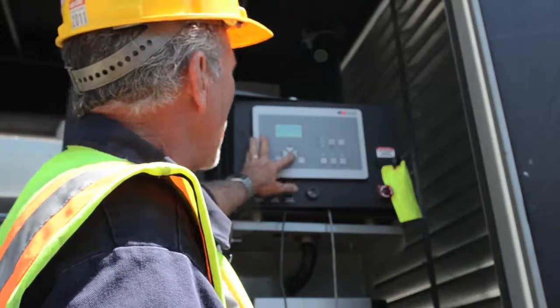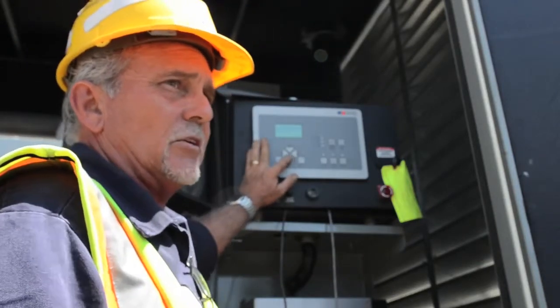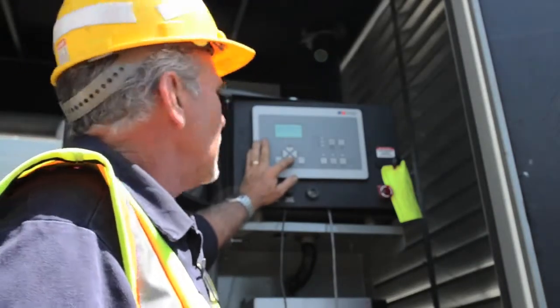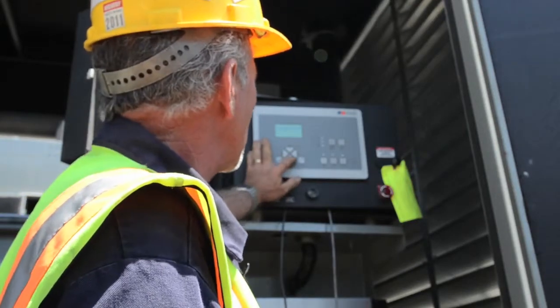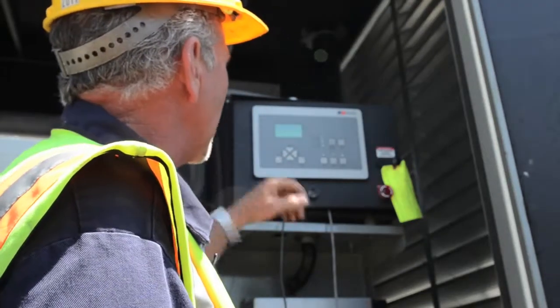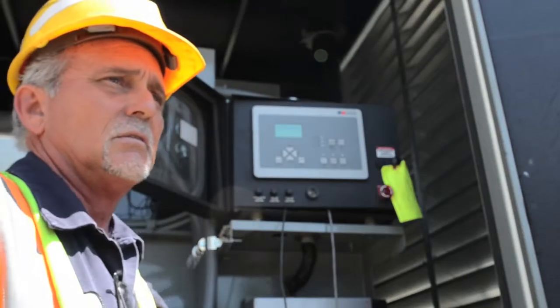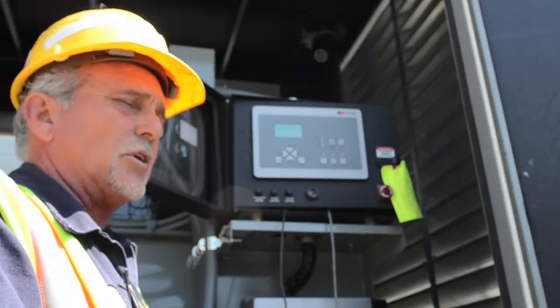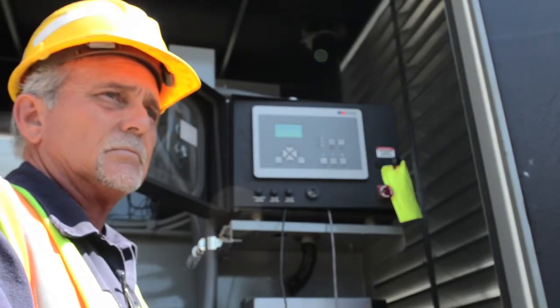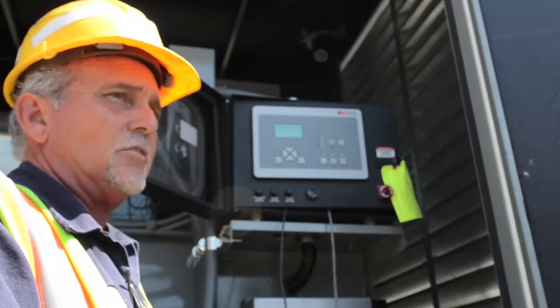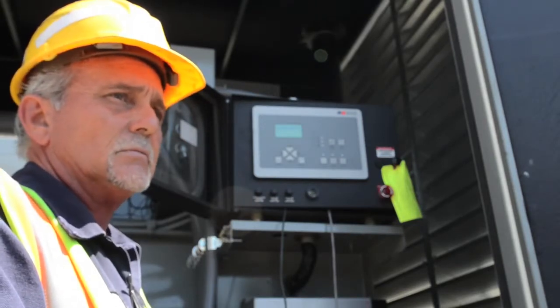But all the basic information I'll ever need is right here at your fingertips. I can go through and look at it and say, how much unloaded runtime do I have on it? Oh, I got an hour and 17 minutes. Most of the time the loaded runtime on here is from when we load bank tested. That record is burned into it. The only person that can reset it is me.